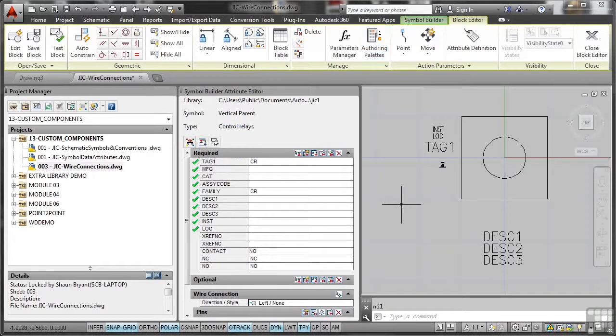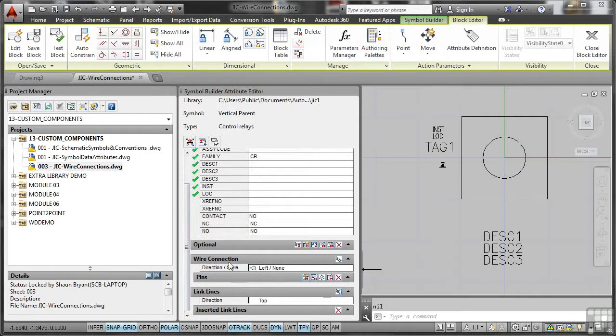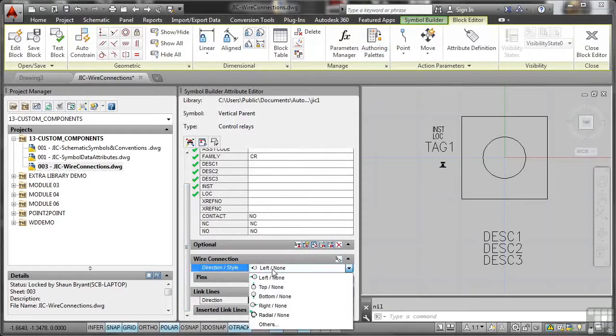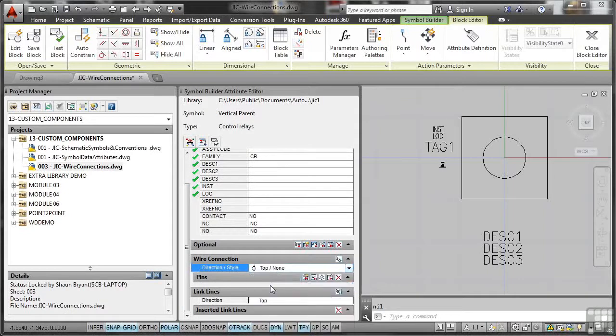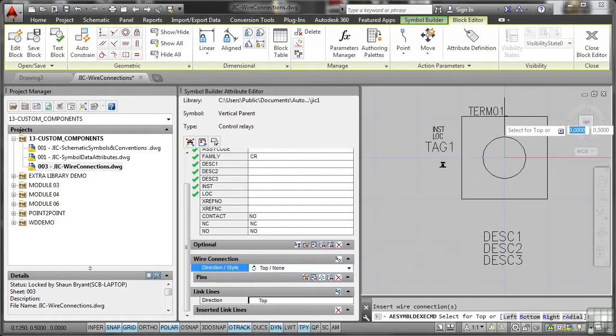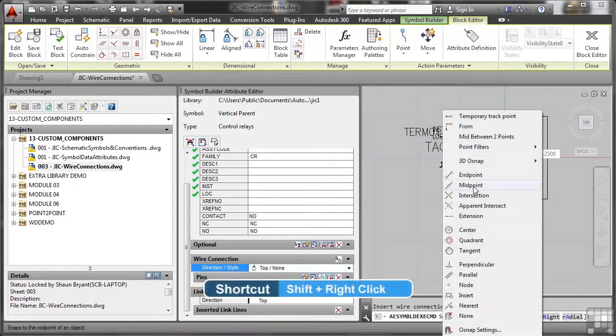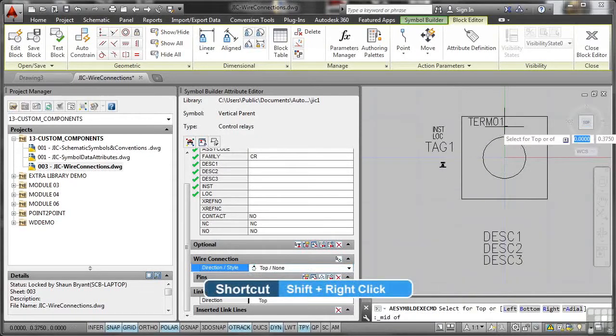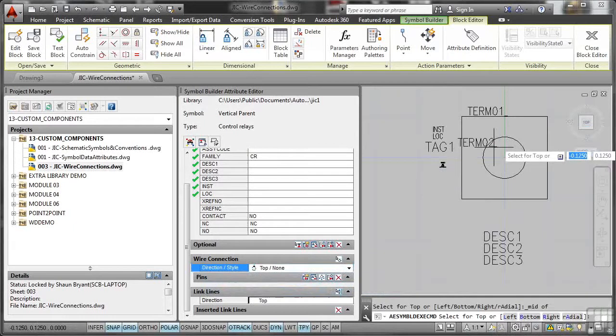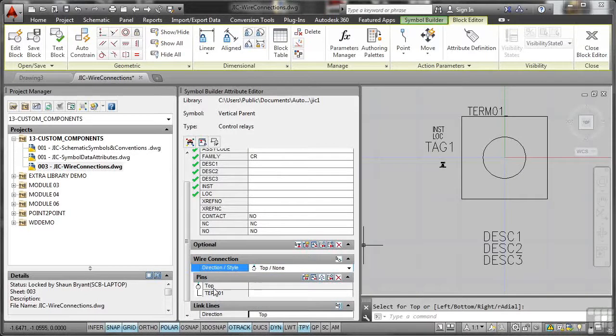Now the reason that it hasn't updated the wires is because we have no wire connections on this just yet. They're right here, so we can see wire connections there, direction style. So what we need to do is set some new wire connections. So I'm going to go for a top, none, and insert that wire connection right there. But what I'm going to do is shift and right click and make sure it's on the midpoint snap of the block itself there like that. And then I'm going to press enter. That's the first one added, and there it is there, terminal 1, and it's at the top.